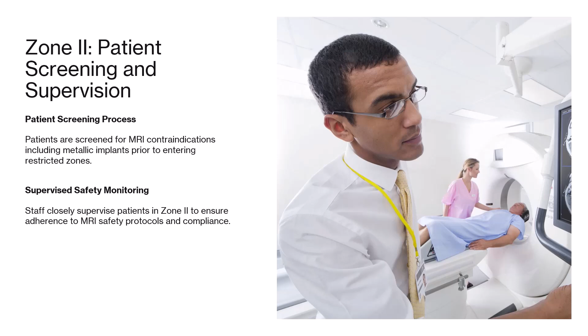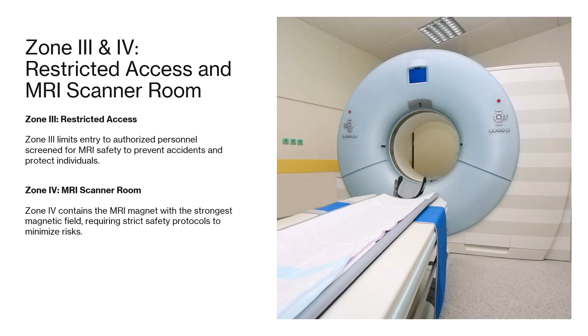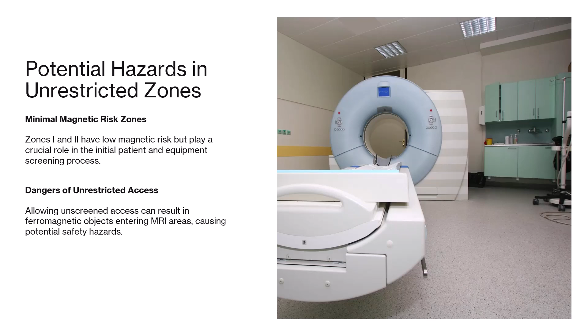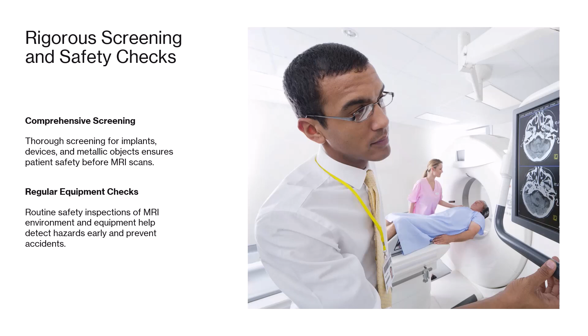Zone 3 restricts access to authorized personnel screened for MRI safety, serving as a buffer before the MRI scanner room. Zone 4 contains the MRI magnet itself, where the magnetic field is strongest and safety risks are at the highest. Zones 1 and 2 have minimal magnetic risk, but are critical for initial screening. Unrestricted areas without proper screening can lead to dangerous situations, such as ferromagnetic objects entering the MRI field. Comprehensive screening for implants, devices, and metallic objects is critical. Regular safety checks for the MRI environment and equipment help identify hazards early.